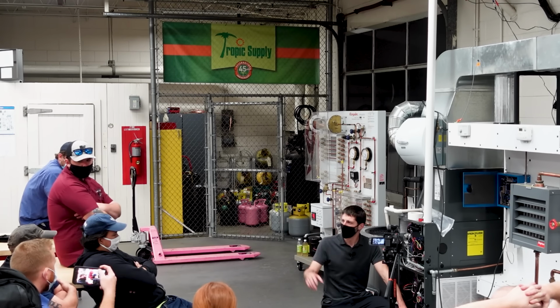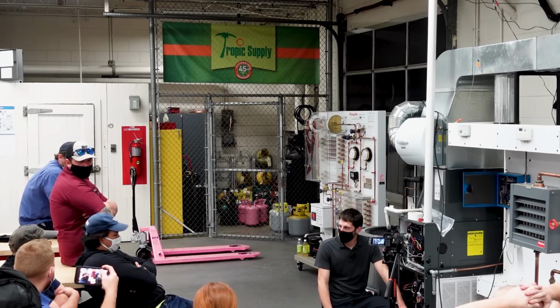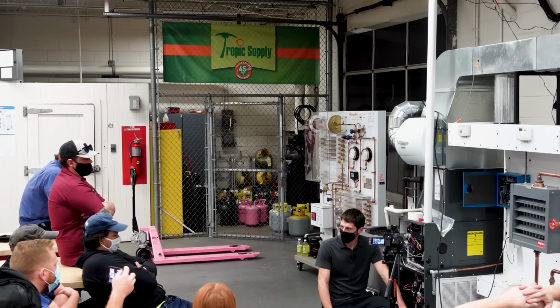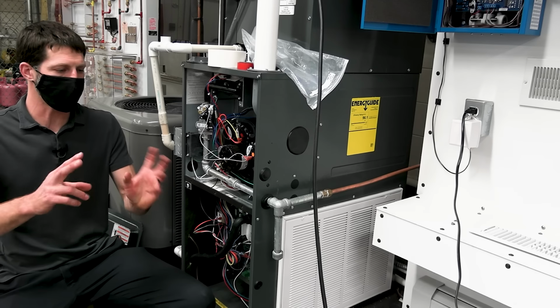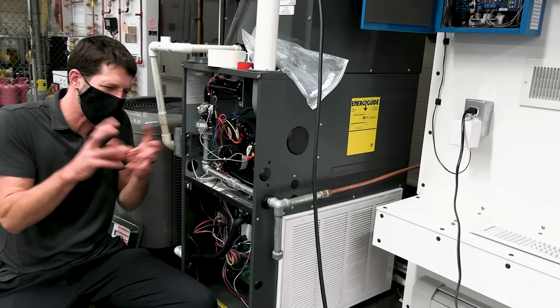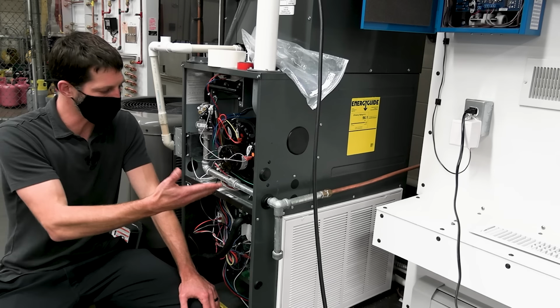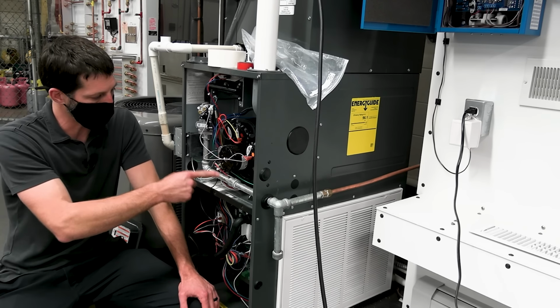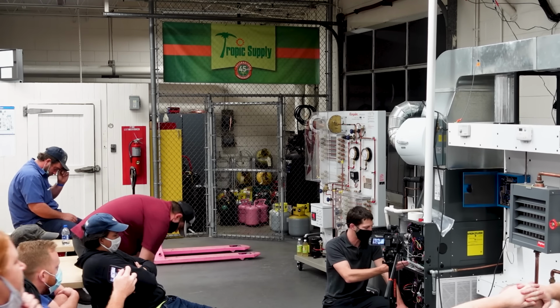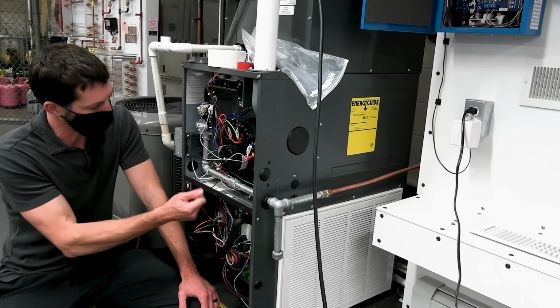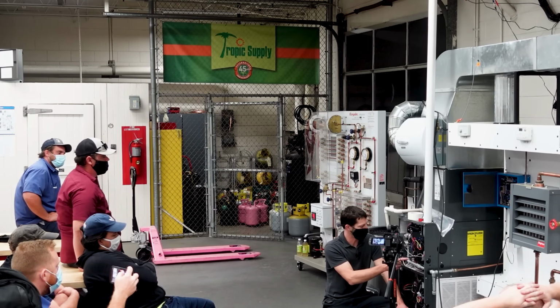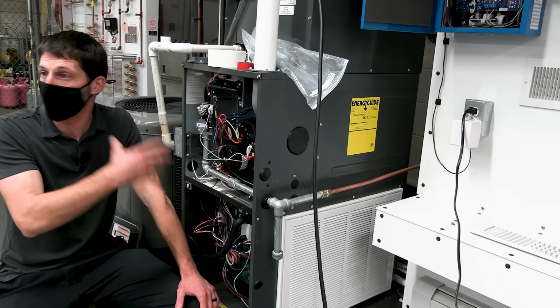Also, when you pipe those together, it's a good idea to use some type of thread compound versus just tape. Yes. There are some types of Teflon tapes that are rated for fuel gas, but typically we call it pipe dope or thread sealant. This one's a Teflon based one. Absolutely have to use your thread sealant on all the threads, and that seals in the joint.